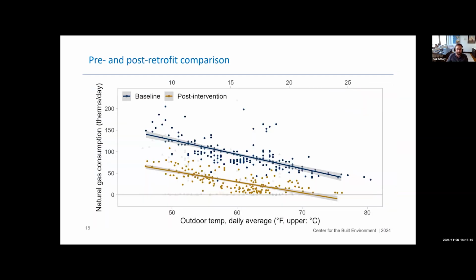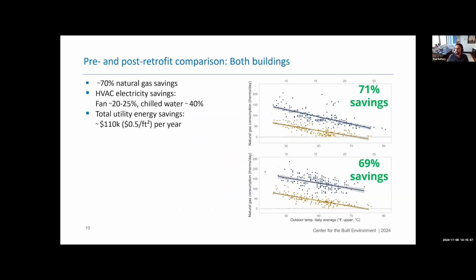And combined, those two effects had this impact that you see here. On the x-axis, you have the average outdoor temperature each day, and on the y-axis, you have the measured natural gas consumption in therms per day. This is actually the PG&E meter bill data, so this is the entire building's gas use that day. The blue line is the pre-retrofit condition, and the yellow is the post-retrofit condition. And this is about a year's worth of data here. And what you're seeing is about 70% measured annual natural gas savings in this building. But we did it in another building, and exact same result, about 70% measured natural gas savings.